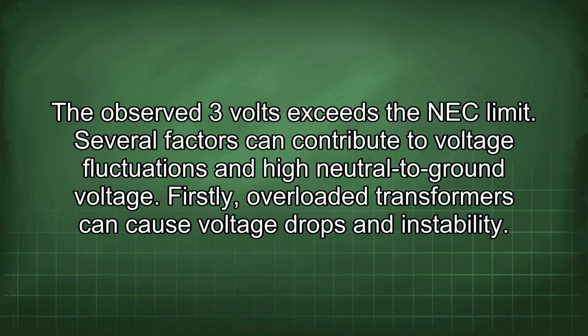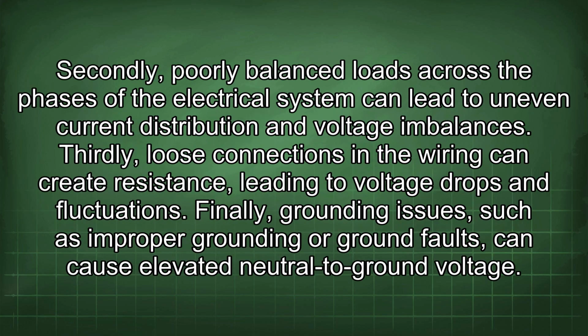Several factors can contribute to voltage fluctuations and high neutral to ground voltage. Firstly, overloaded transformers can cause voltage drops and instability. Secondly, poorly balanced loads across the phases of the electrical system can lead to uneven current distribution and voltage imbalances. Thirdly, loose connections in the wiring can create resistance, leading to voltage drops and fluctuations. Finally, grounding issues, such as improper grounding or ground faults, can cause elevated neutral to ground voltage.